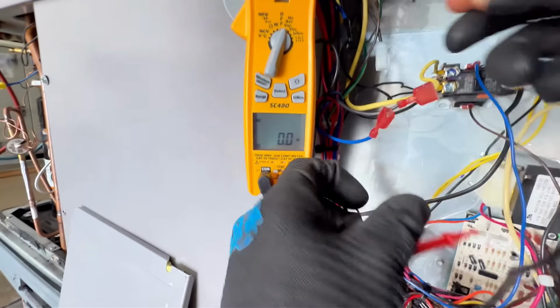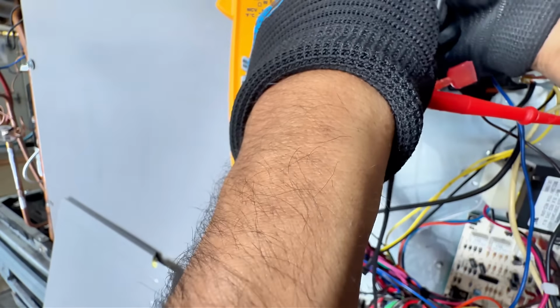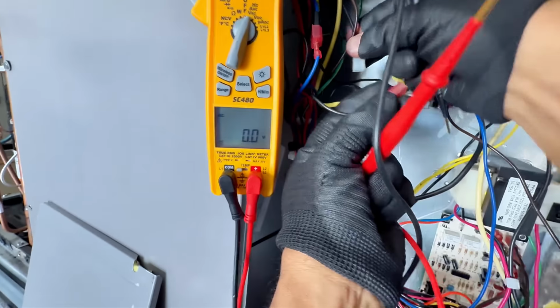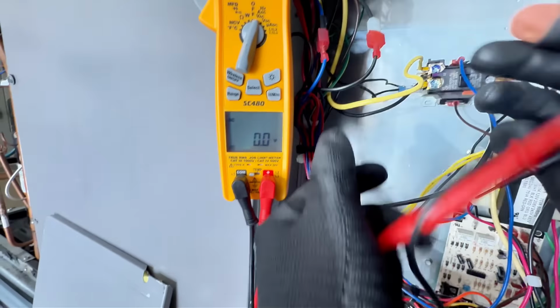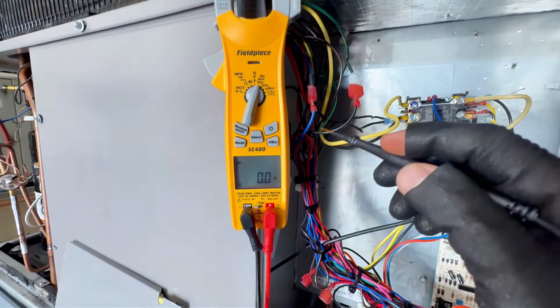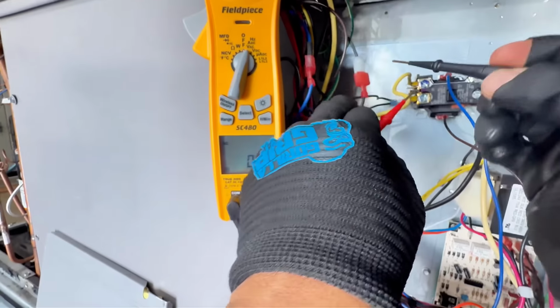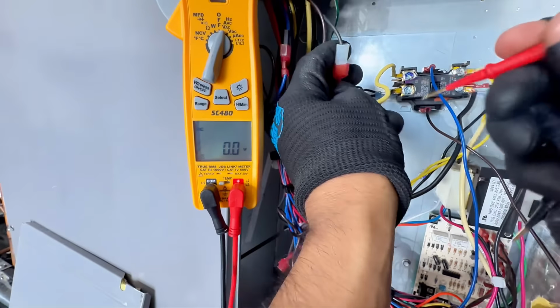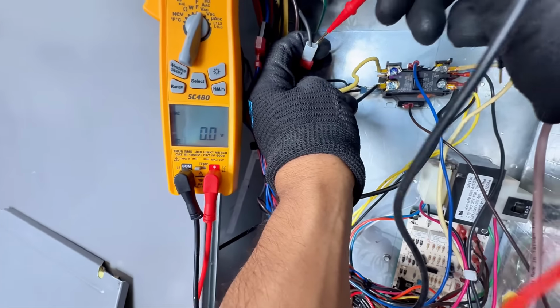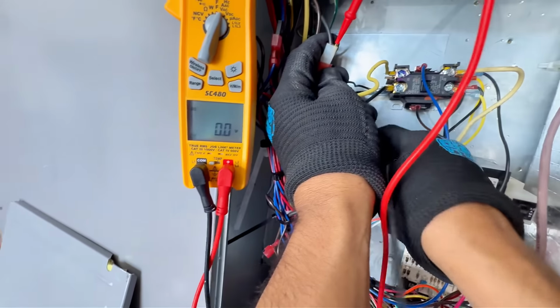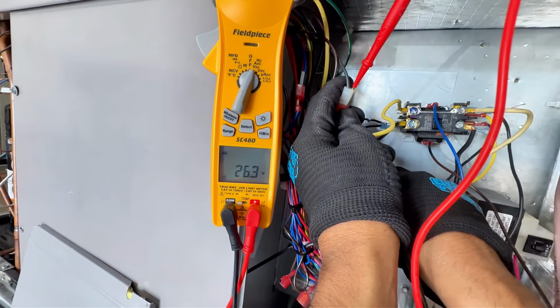So I'm going to go ahead and reconnect the blue one over here. Okay. And then this one here. Okay. So we are sending 24 volts. It is going and then it is coming back. And I confirmed it by checking continuity, but then you can just check this too. Put one here and one on common. You see, I'm getting 24 volts. So 24 volts is coming back.